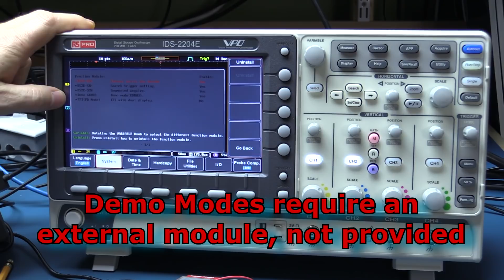Probe compensation, this will control what frequency comes out of this test probe pin here, which allows you to set up the oscilloscope probes. If I just plug these in a second, so if I take one of these channels, let's just take channel 1, put it on the probe compensation pin. Alright, so they're both set to 1 volt per division. Fit to the screen, and there we go. Now we've got a little bit of noise, which is probably being picked up because of some of the devices I've got around in the lab here.